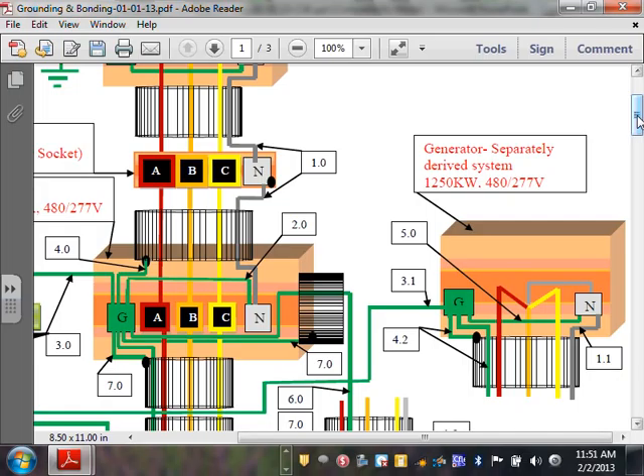If you tie all the neutrals together, which you have to make this decision for the most part, then you don't have a separately derived system. Either way, this happened to be a separately derived system. So I created a new neutral, and when I brought these into the switchgear, guys, the way they do it in the parallel switchgear is they have 4-pole circuit breakers, and you open them.